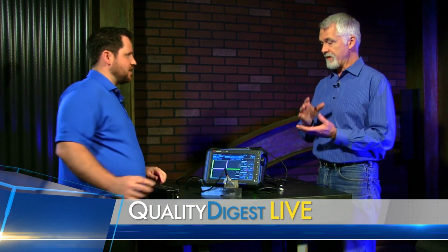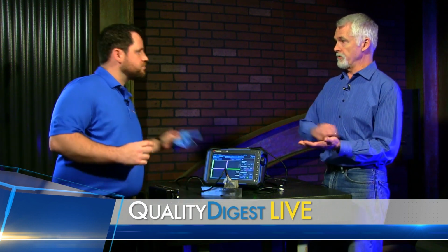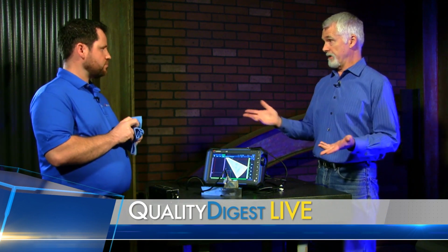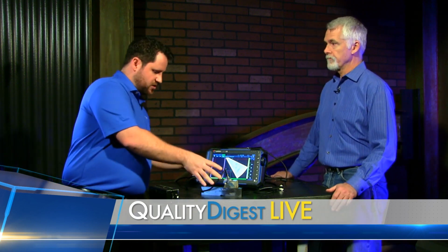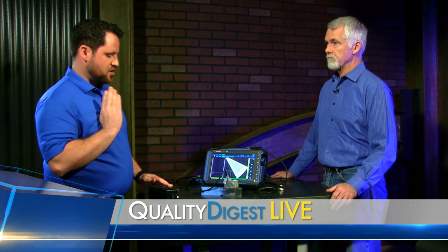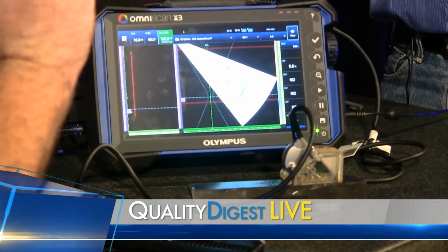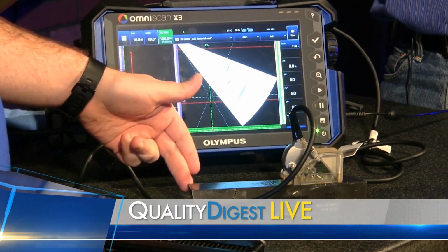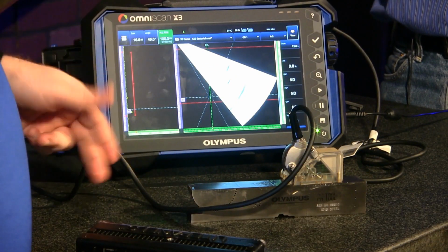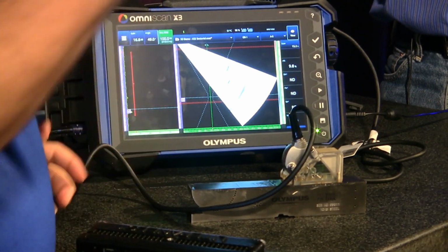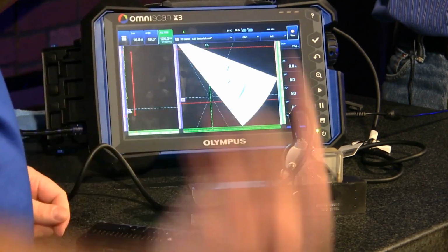So they basically have a calibration artifact that they use to calibrate against, right? Correct. They would have a block similar to this, either with maybe a notch cut into the top or bottom of the block, maybe a side drill hole, or even on this block here, you have a radius on this left-hand side that you would use to adjust either for distance or maybe adjust for amplitude.